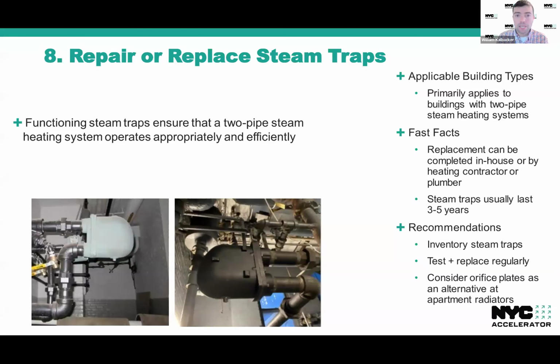Thank you. Yeah, just jumping right back in. So prescriptive measure number 8 revolves around steam traps. Steam traps are an integral part of two-pipe steam systems, and making sure that they are functioning properly is the best way to make sure that your two-pipe system is operating efficiently. Essentially, a steam trap is a device throughout the distribution of the two-pipe steam system that keeps steam where it should be and keeps it out of where it shouldn't be. When you have steam where it shouldn't be in the return side of the steam system, you are using and producing more steam than you need to, and you are also opening yourselves up to risks of equipment damage. So it's just generally advisable to replace or repair broken steam traps when they need to be.